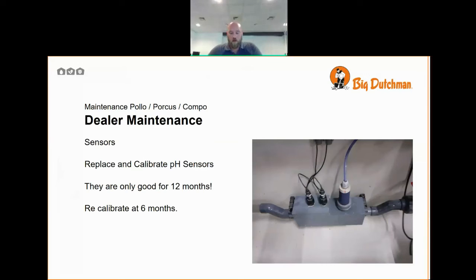Perfect. The pH sensors themselves are an electrode inside a glass case. So as the electrode is producing a millivoltage, over time the electrode will begin to corrode and be used up. So therefore, they're only considered effective enough for 12 months.